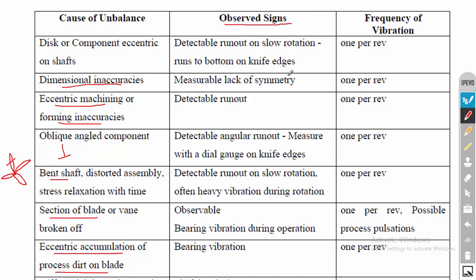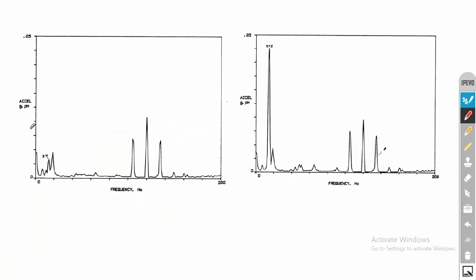These are the observed signatures. The frequency of vibration for unbalance: if you measure the vibration and convert the time domain signal to the frequency domain, you will see a peak at one revolution — that is, a peak at the RPM speed. This is the identification tool for unbalance. For a perfect system, there is no high peak. For an unbalanced system, there is a tall peak at the operating RPM. You must convert RPM to hertz, and the peak will be exactly at the operating speed.